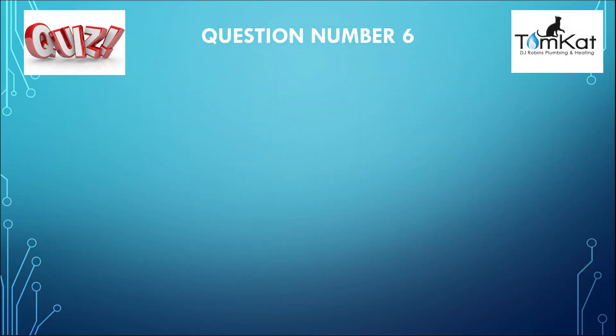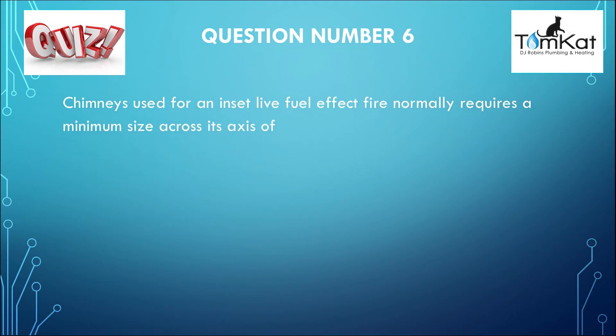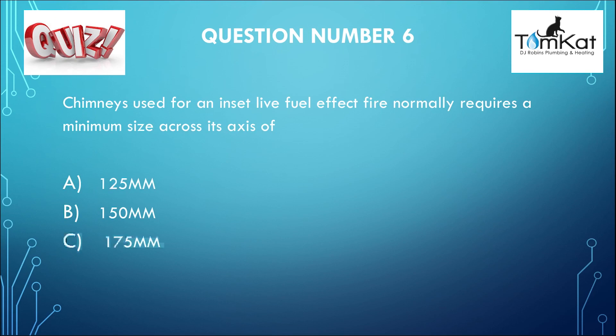Question number six: Chimneys used for an inset live fuel effect fire normally require a minimum size across its axis of A, 125 millimetres; B, 150 millimetres; or finally C, 175 millimetres. That is the end of question number six.